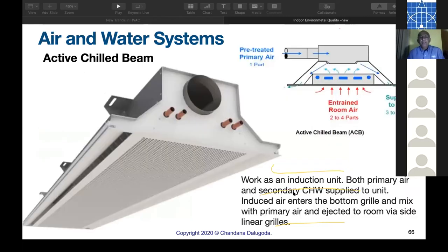This is an active beam. Now these chilled beams look like a beam. You have a series of chilled beams together. In an active beam, like an induction unit, you send primary air, and here you send secondary chilled water, similar to an induction unit. Of course, this is the induction principle, active beam. So again, the constraints are similar.